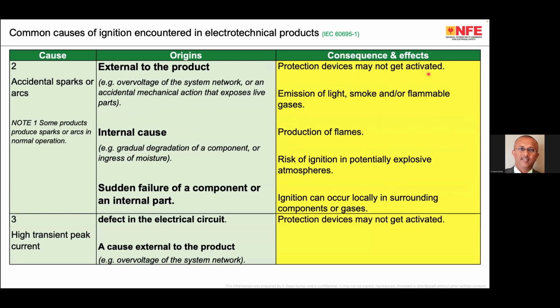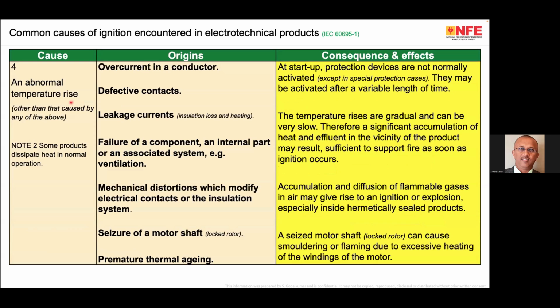The preventive measure is automatic disconnection of supply. The second cause of fire is accidental sparks or arcs, external to the product or internal to the product, and sudden failure of a component or an internal part. The consequences are that protection devices may not get activated. Again, the same reason here. Emission of light, smoke, and flammable gases, production of flame, risk of ignition of a potentially explosive atmosphere. Ignition can occur locally in surrounding components or gases. So basically, accidental sparks or arcs is also an identified reason; the origin is identified and the consequences are recorded. Then the transient current, then abnormal temperature rise due to overcurrent, defective contacts, earth leakage, and so on.